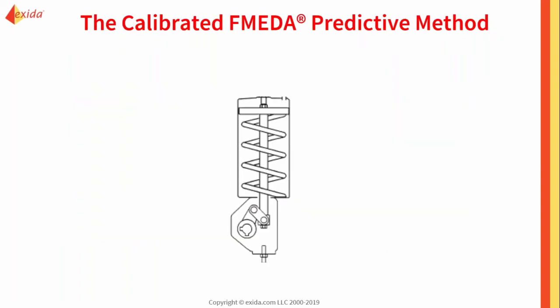The FMEDA method is looking at that strength of the design. Once again, it can be a newly designed device or an old designed device, and we took a number of techniques and combined them together: FMEA, with diagnostic analysis, with the military handbook 217, and all combined to look at how the parts could possibly fail when different stresses of the environment are thrown at it, considering their diagnostics.